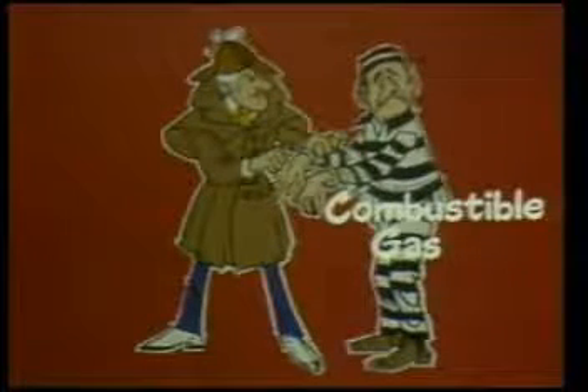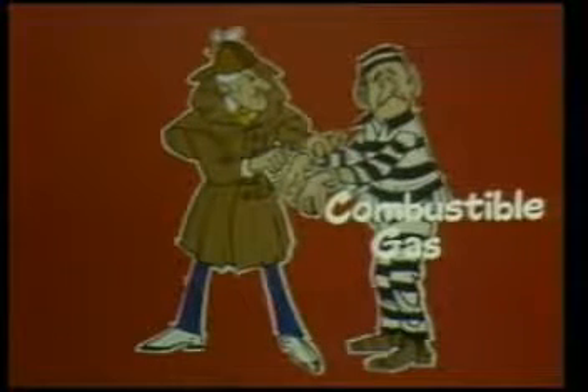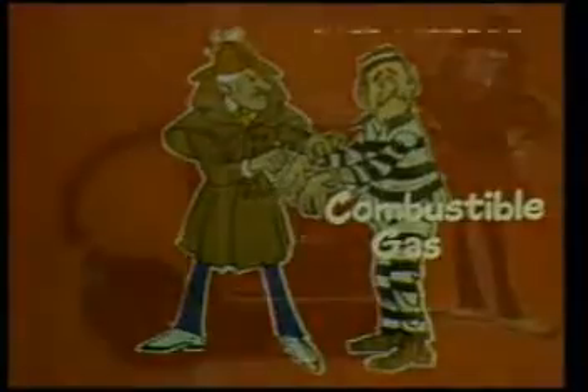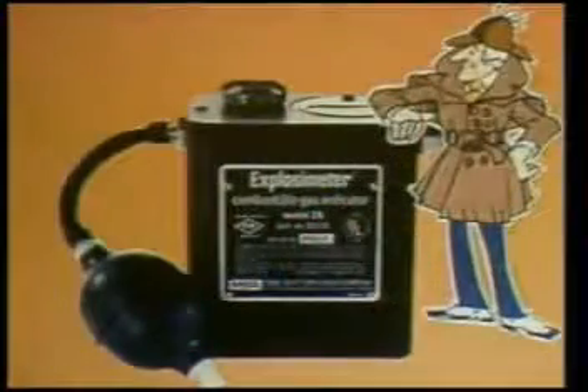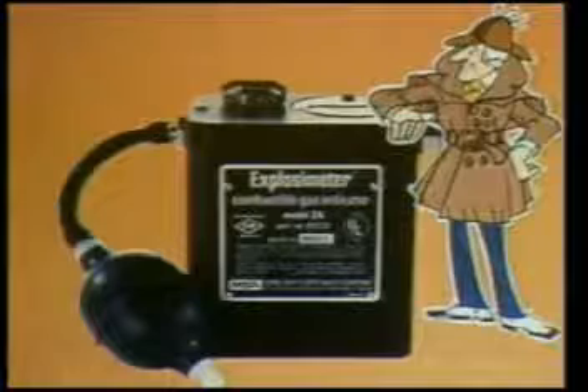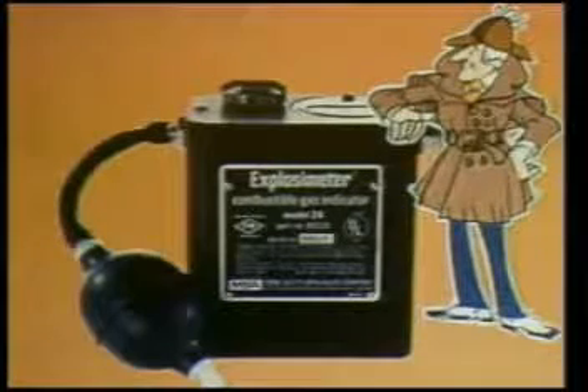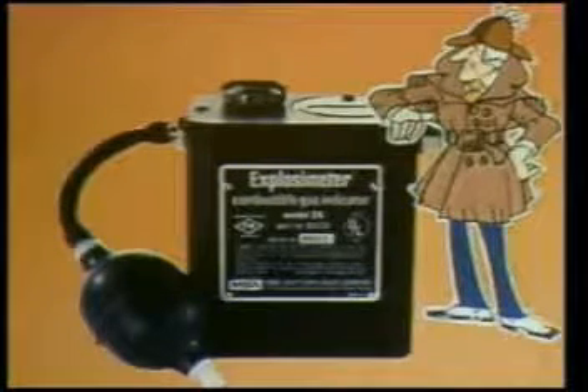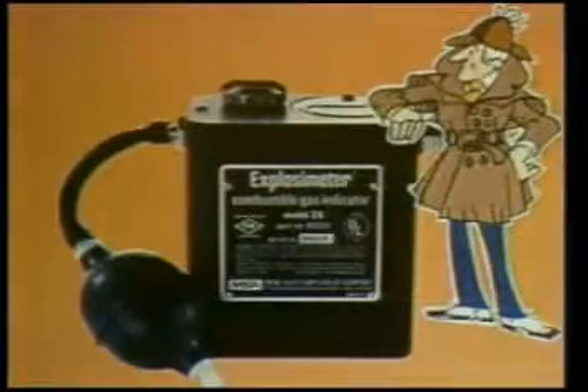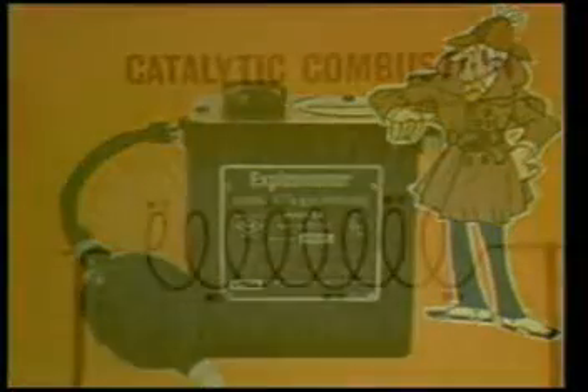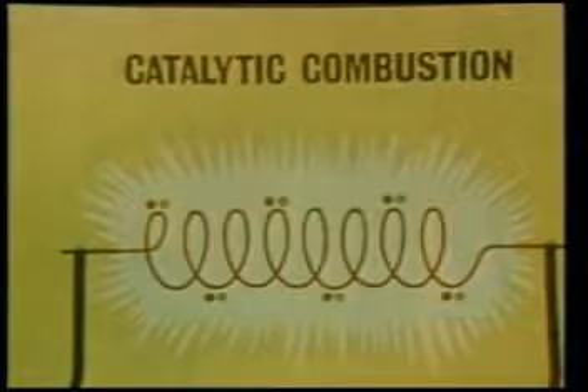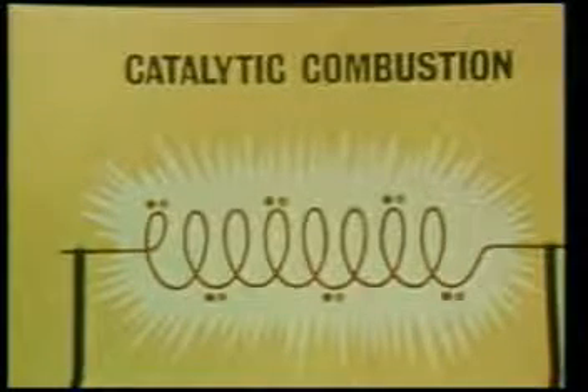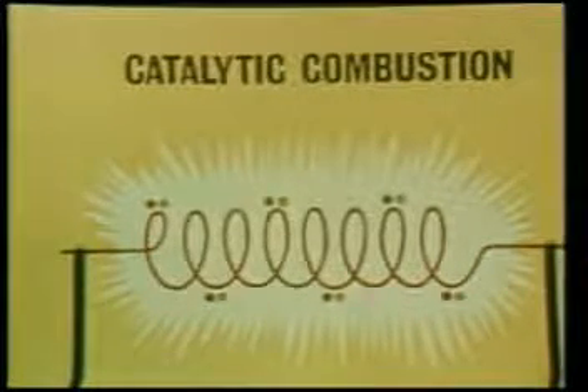Okay, now that we know more about our suspect, combustible gas, let's find out how this instrument called an explosimeter indicator works. As the name suggests, it's designed to detect the presence of explosive or combustible gases in the air. It's based on the principle that a measurable amount of heat is released when a combustible gas or vapor is burned. Here, the combustible is burned on a coil of platinum wire.